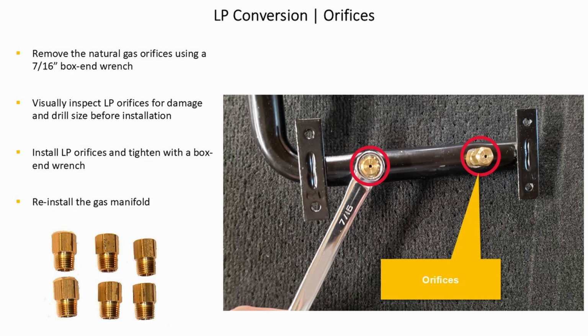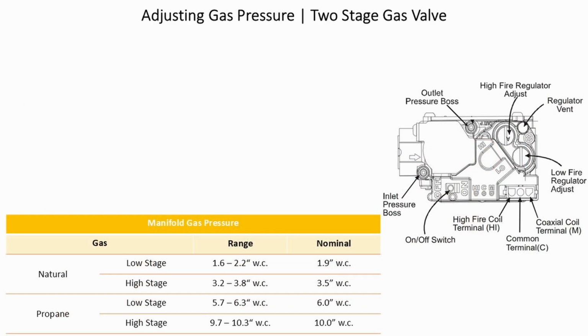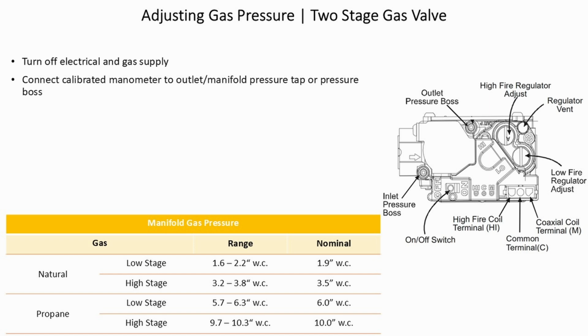Reinstall the gas manifold. Adjusting gas pressure on a 2-stage gas valve. Turn off electricity and gas supply. Connect a calibrated manometer to the outlet manifold pressure tap or pressure boss.